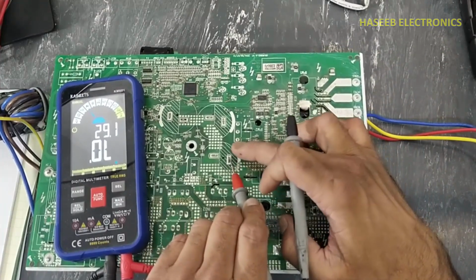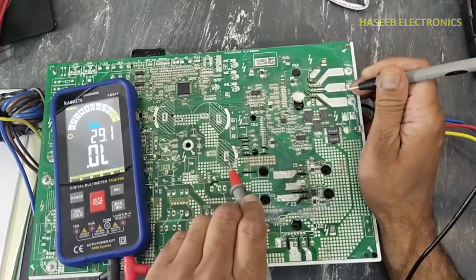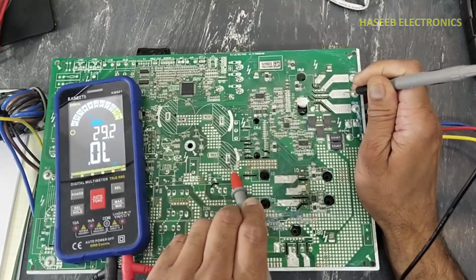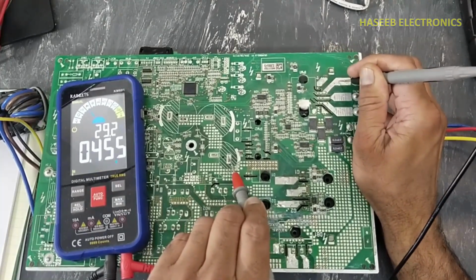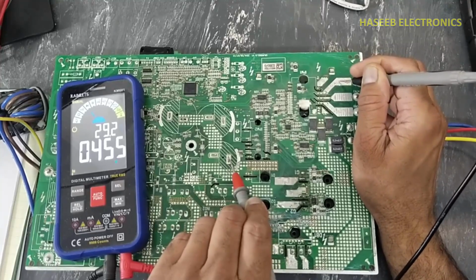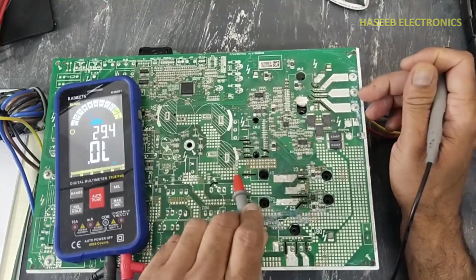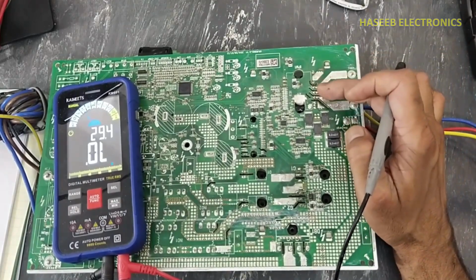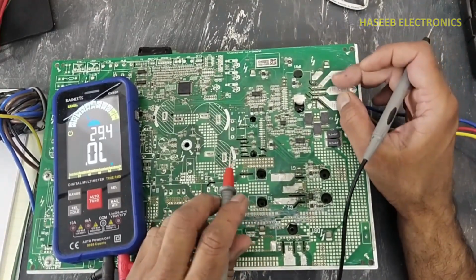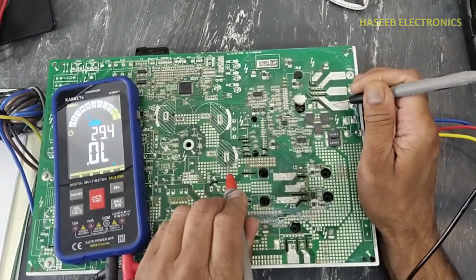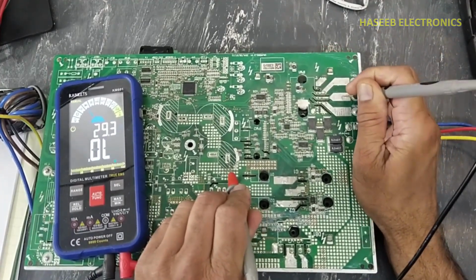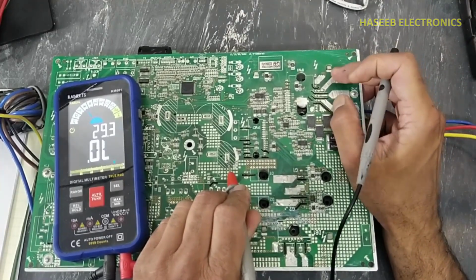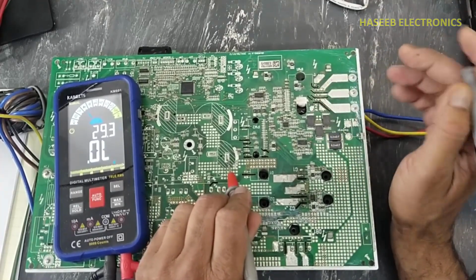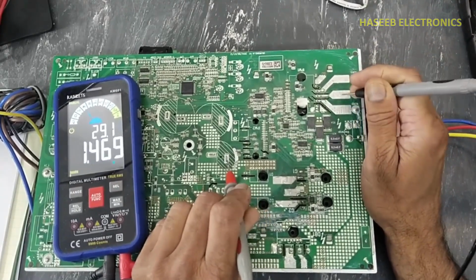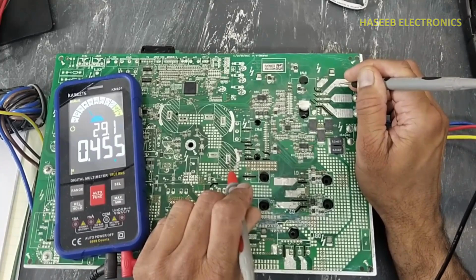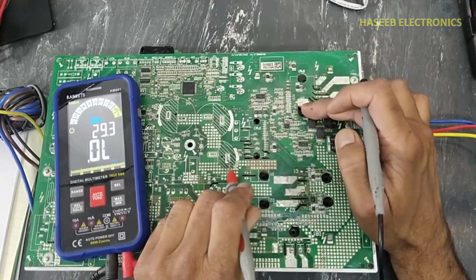While connecting the red lead at the negative terminal, connect the black lead at UVW. It is giving 0.45 volt on each pin. So it is the internal diode for the low side IGBTs. That means it is good. If we find continuity here, at that time the IPM IGBT is bad. If we find continuity here, or we find any one diode open, we need to replace the IPM.